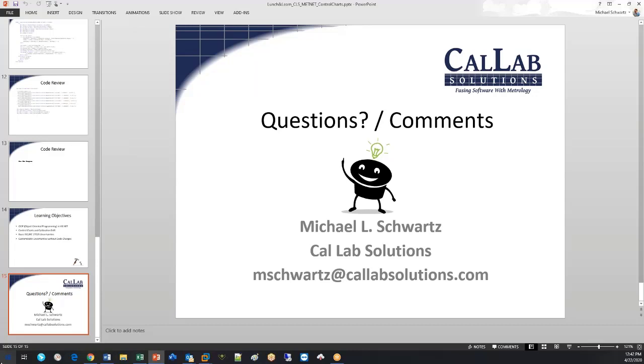Oh, yeah. That would be something outside of the scope of what I'm trying to do with this. I understand. I'm just saying, that would be covered in the calibration uncertainty that the vendor gives you. Yeah. Well, we don't know yet. That's something you have to investigate. If they don't include that, you need to find a different vendor. Yeah, that's what I'm saying. The way Jeff called this, I think he presented just last week as well, and it's similar. I'm just asking about the definition of drift, and you have to actually find out. It's not just taking those data and doing the linear regression.